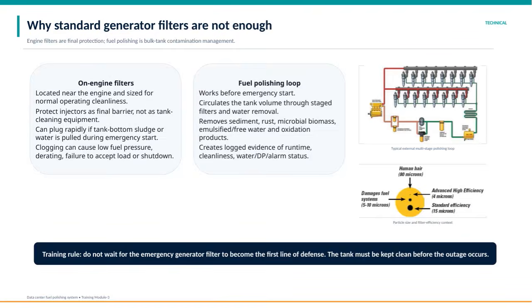Here, we're addressing why relying solely on standard generator filters isn't sufficient for protecting your engine. The filters located directly on the engine act as the final line of defense and are designed for maintaining normal cleanliness during operation. Their primary role is to protect the injectors, but they are not meant to clean the fuel tank itself. This means that if sludge or water from the bottom of the tank enters during an emergency start, these filters can quickly become clogged.